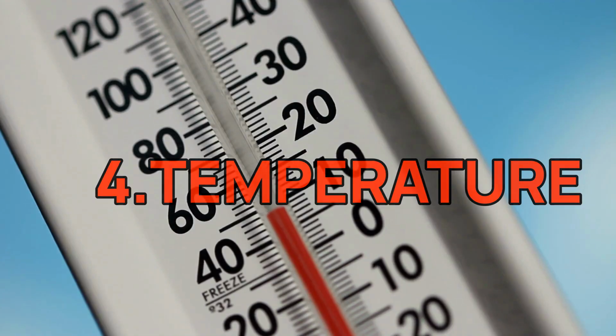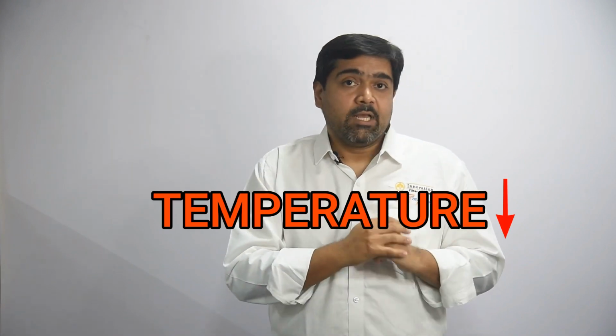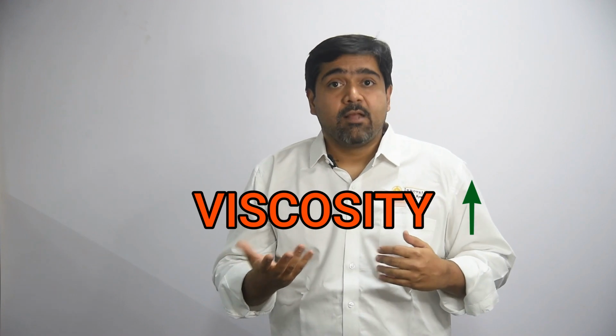Knowing the temperature of the fluid while designing the filtration system is extremely important, especially in the case of oils, because the viscosity of the oil changes with changes in the temperature. As temperature reduces, the viscosity increases. That is, the oils become thick, and vice versa. Now, as seen earlier, the viscosity affects the flow rate, and hence temperature also affects the flow rate.